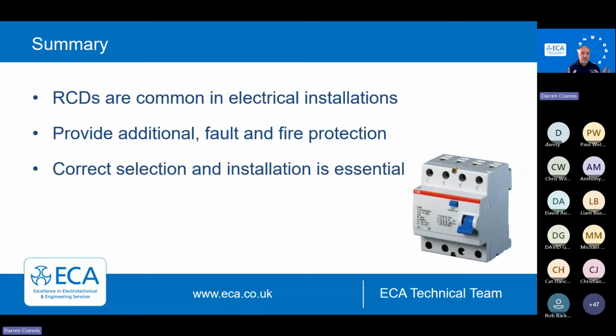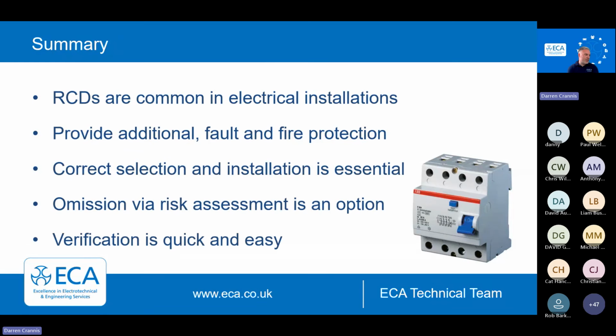So to summarise this, RCDs are extremely common in our electrical installations. They do much more than just protecting the user. Socket outlets, additional protection, fault and fire protection are also key benefits of these. We've had a quick tour over a lot of these today, but there are many RCDs. They do many different things. They have many different values, and they cost many different pounds. So we've got a whole abundance in the last five years of different RCDs we select, and getting them right, we can still risk assess them out in certain situations, and we've explained that today. And when you come to inspect and test these, again, it's dead simple. Could save on some periodic inspection time.